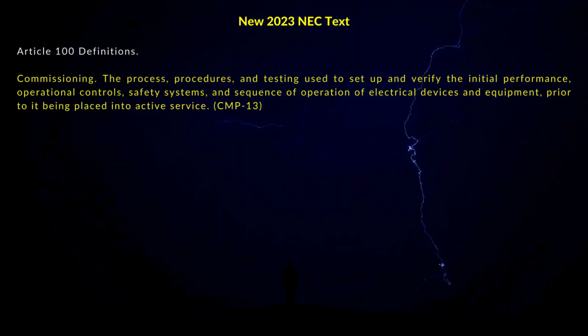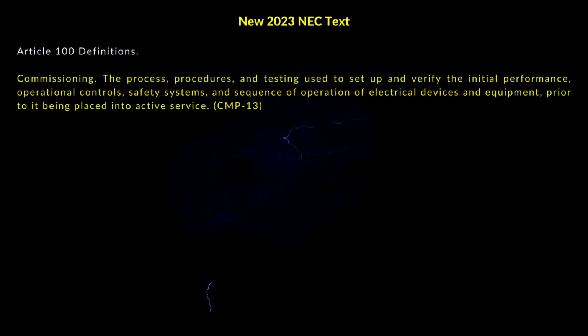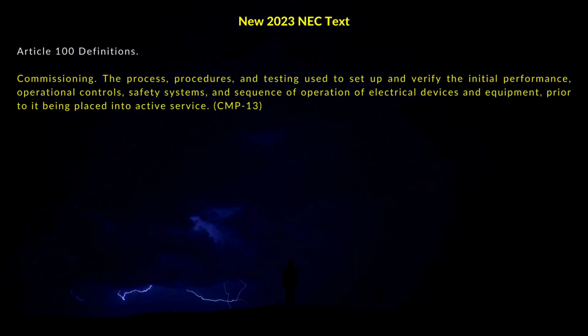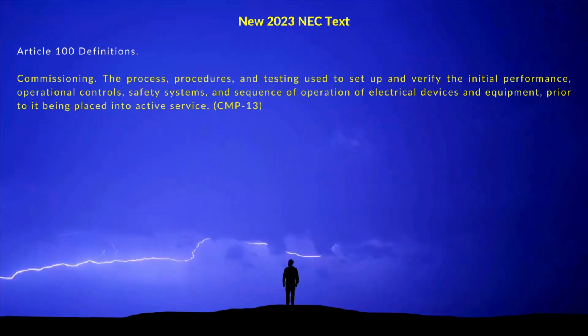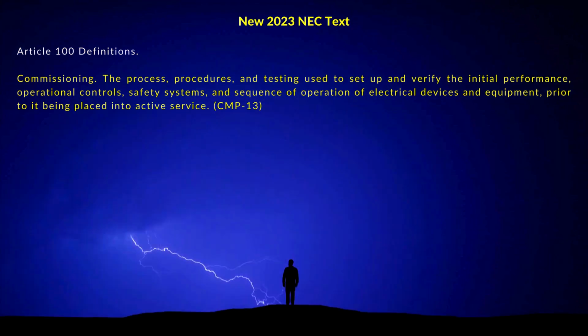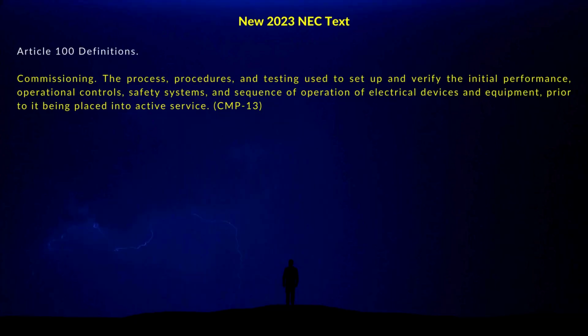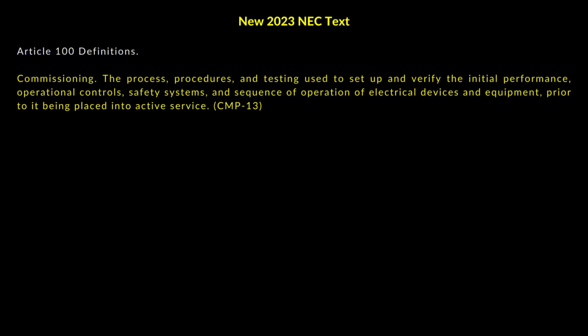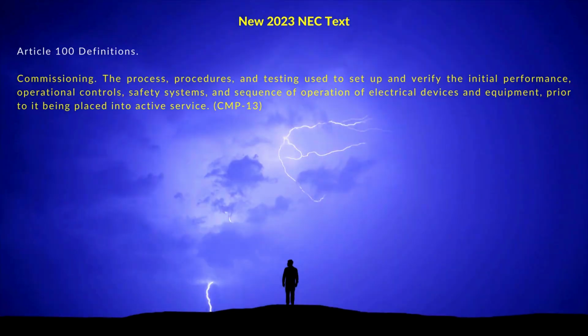The new 2023 NEC text, for commissioning, states that the process, procedures, and testing used to set up and verify the initial performance, operational controls, safety systems, and sequence of operation of electrical devices and equipment prior to it being placed into active service.